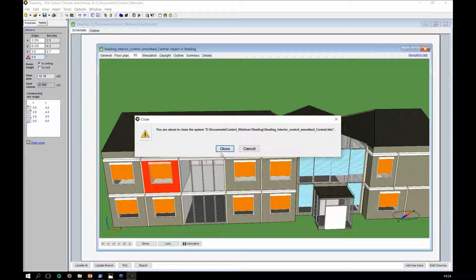Drastic effect. The last case here is exterior control. What if we want a much more realistic type of shading, where we have a sensor located outside the building? I took the same case again, and this time in the supervisory control, instead of the zone sensor, I put, because IDA allows me to access any of the models, and because IDA allows me to log any of the variables, I'm bringing in the shading model and the window facade model and logging the radiation being cast by the sun, basically diffuse and direct, onto that window.